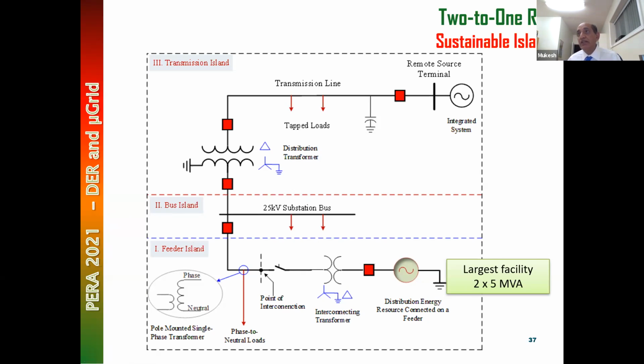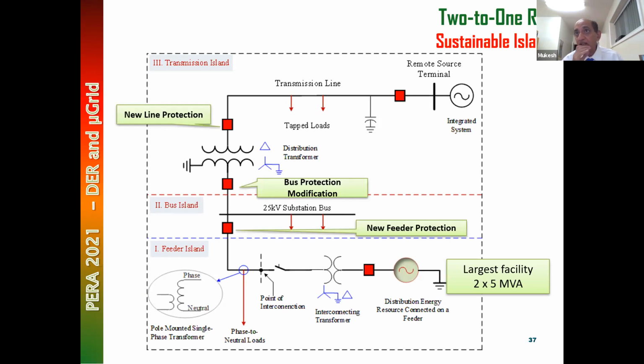So this IPP being 10 MVA required lots of protection upgrades. We had to put in modern microprocessor-based protection here. We had to put in line protection here because the power was bi-directional, and we had to do a little bit of work in the station bus protection. Large generator, large upgrades. We put in new feeder protection, we modified the bus protection, and we put in a new line protection.